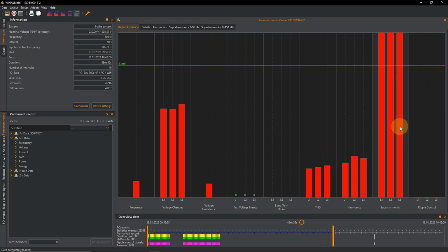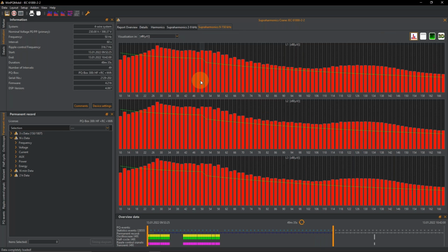But supraharmonics are still there, as I expected. So I will click on my supraharmonics. This opens the tab supraharmonics 9 to 150 kilohertz in my view. I see a lot of bars over here, and obviously the visualization in decibel microvolts. This is because the standards only provide limit values in decibel microvolts. So I see there were many supraharmonics above the limit value.